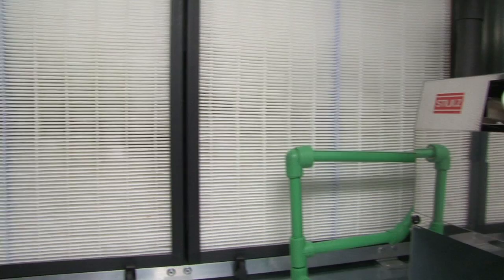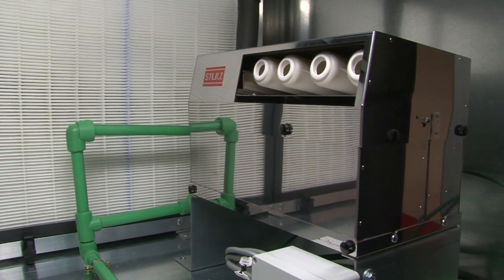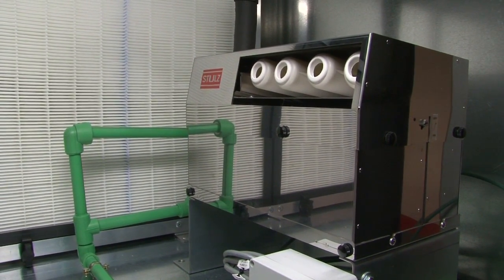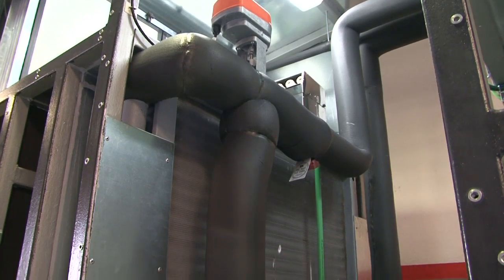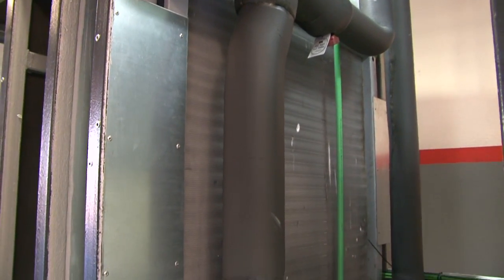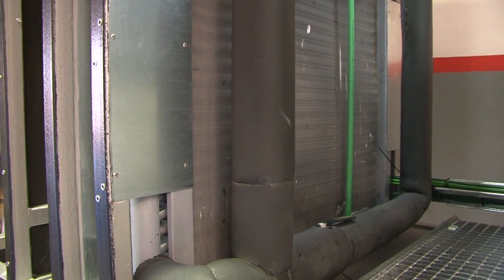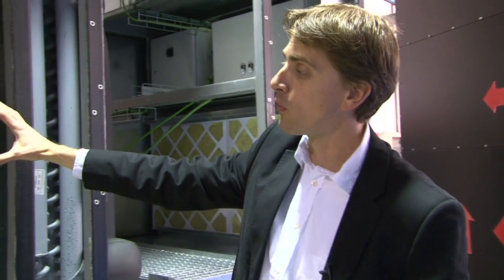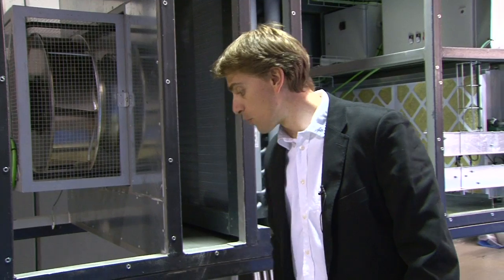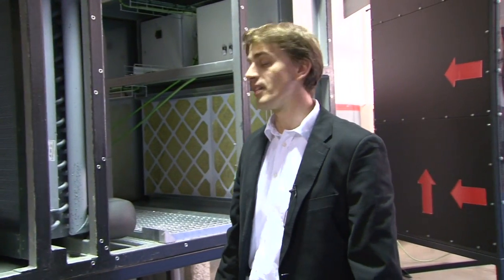We have a humidification stage in this area as well. Then this air will come down towards our coil in order to cool it down if necessary, to the appropriate limits. In other words, if the air outside is cold enough, this unit will not be operating, and basically the fan will be pulling air towards our data center and towards our raised floor, providing cold air towards our data center.